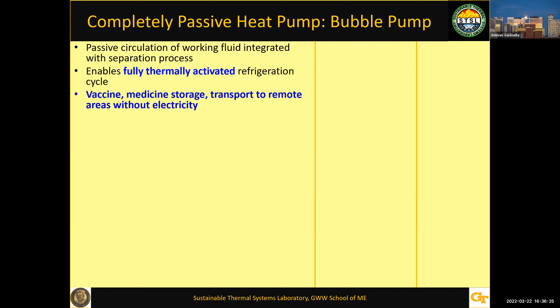It's a fully thermally activated refrigeration cycle. The way it works is, instead of a pump, the actual buoyancy of the vapor and the liquid pumps up that liquid, so it acts as a circulating pump. There are different species in that fluid, in the vapor and liquid, and the partial pressures are different in different parts of the system. Due to this difference in partial pressures, some portion of the cycle is cold, some of it is hot, as you want in a heat pump.